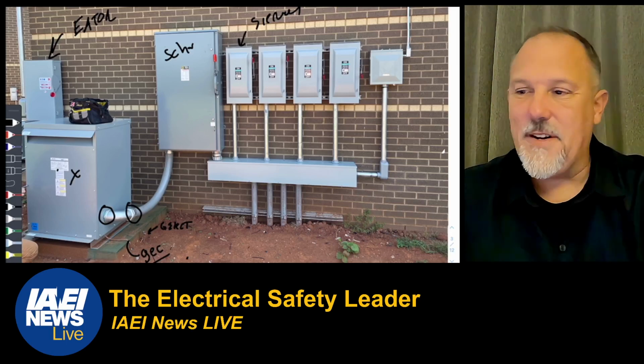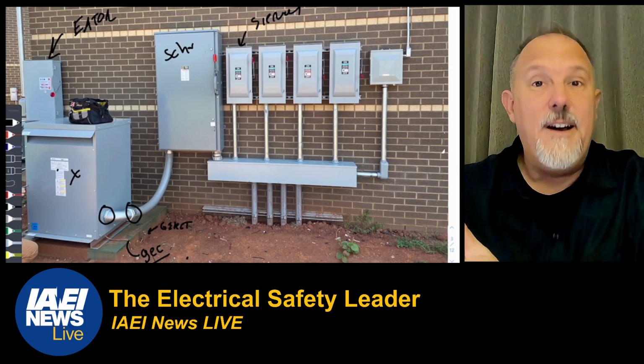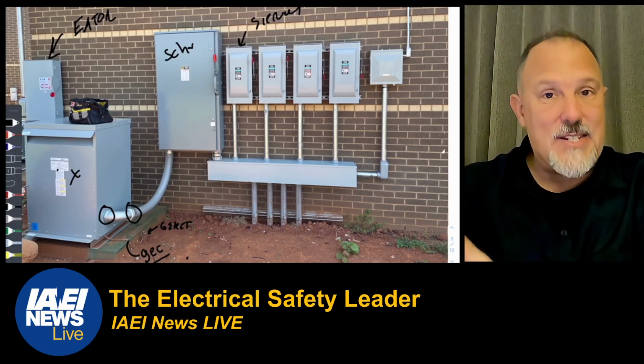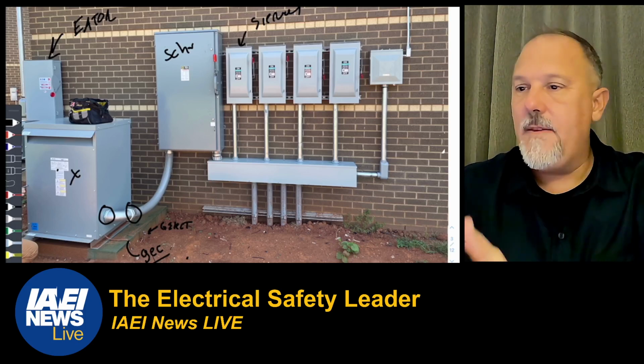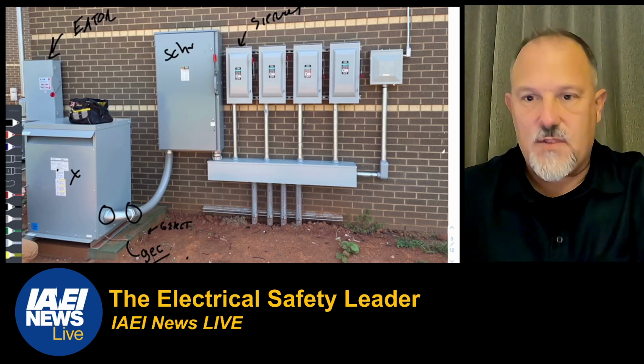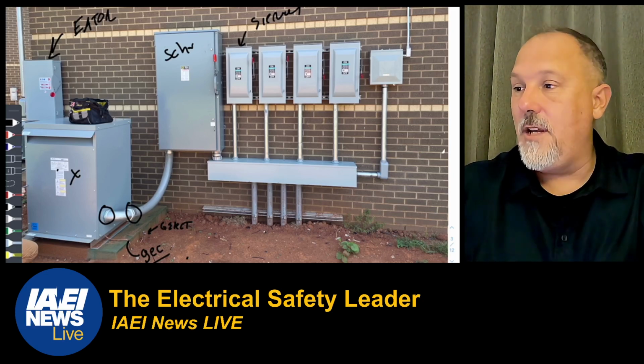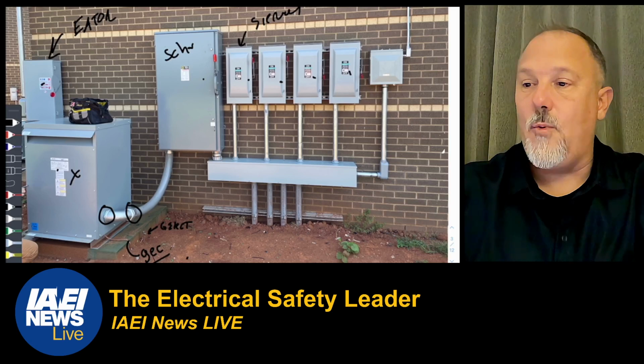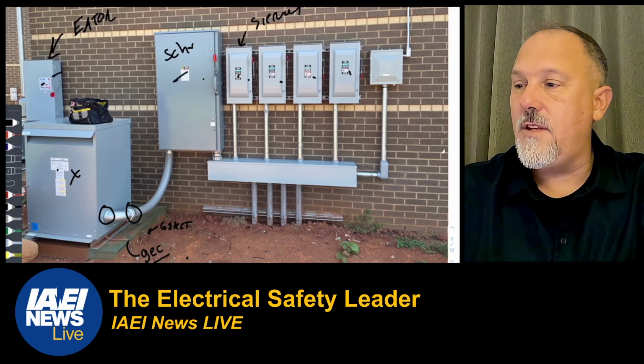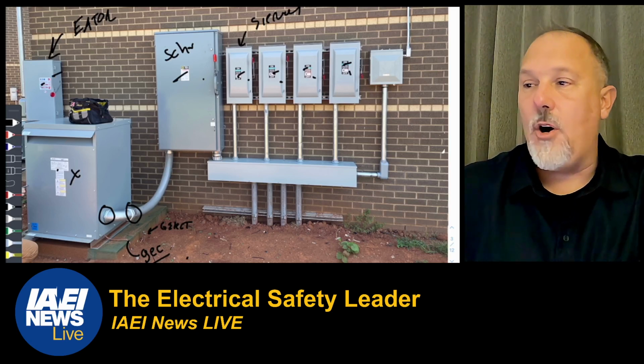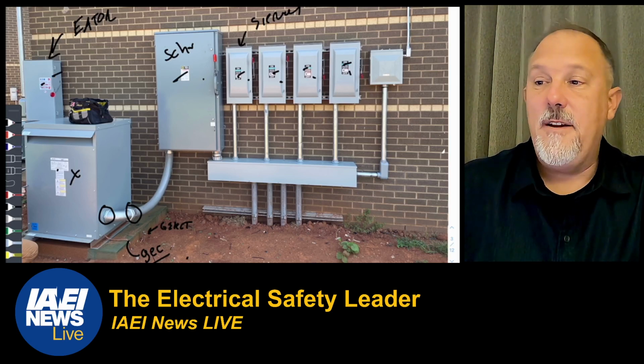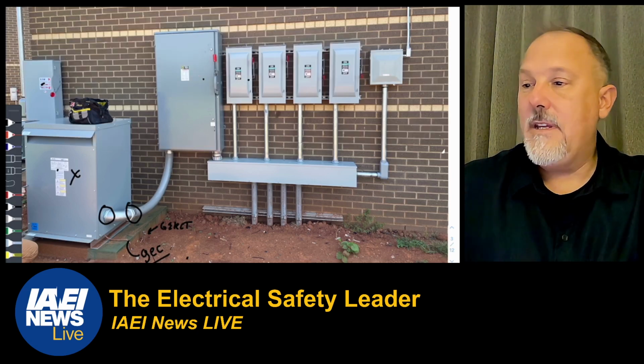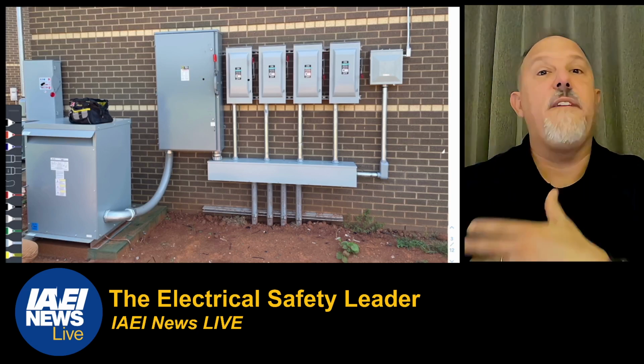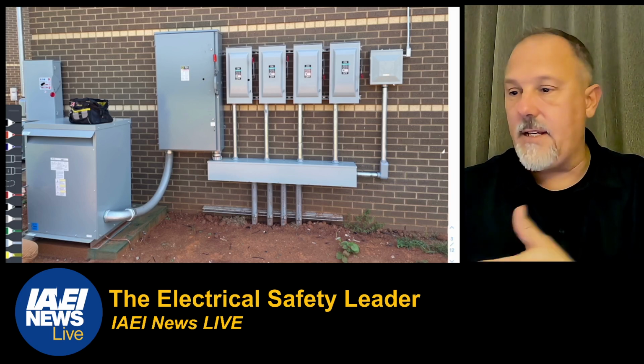So you've got a little bit of a mix and match, which tells you the strength of standards. When products are listed to a standard, there is a base level of performance. We're talking switches here, we're talking transformers, well, basically switches. I mean, you got 1, 2, 3, 4, 5, 6 switches. One's a non-fuse switch. This is a fuse switch, and these are fuse switch. So a whole mess of different types of products, which again gives you an example of just what you might find on job sites, which is, mixing and matching some products is not a bad thing, technically.